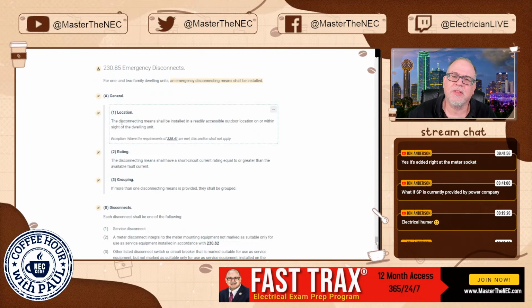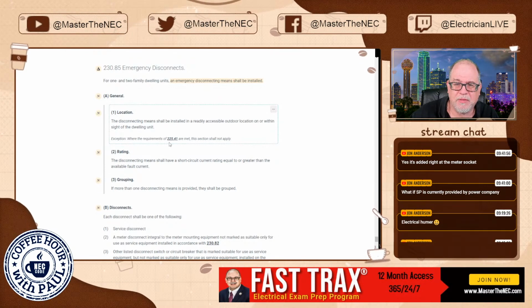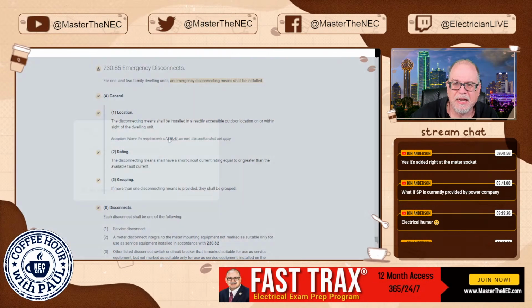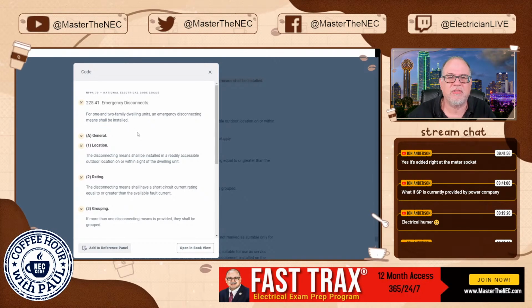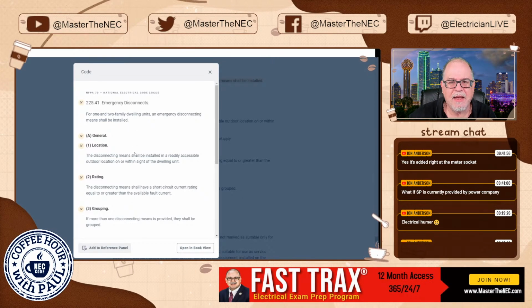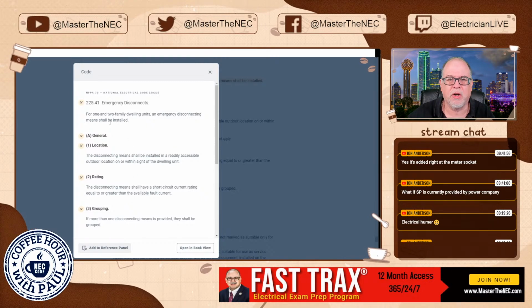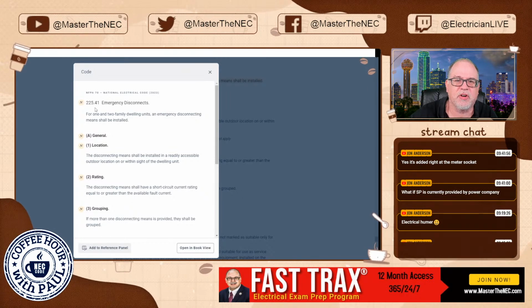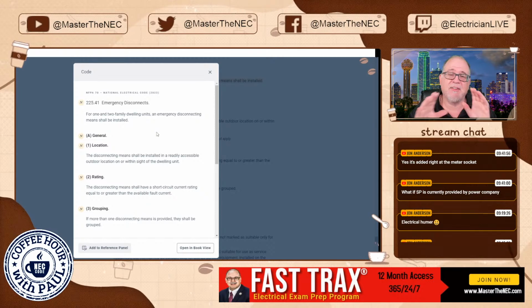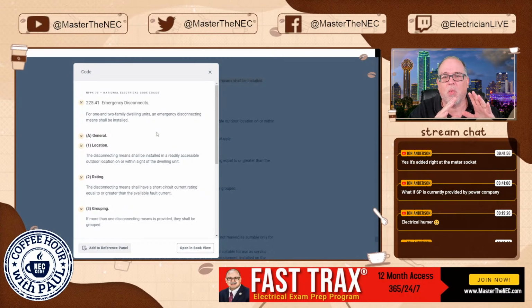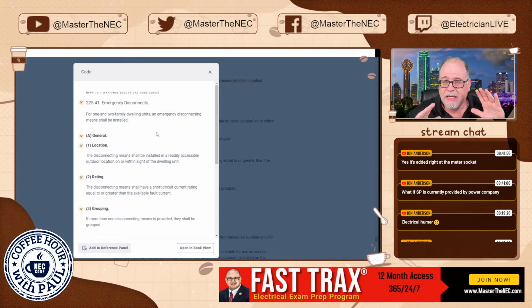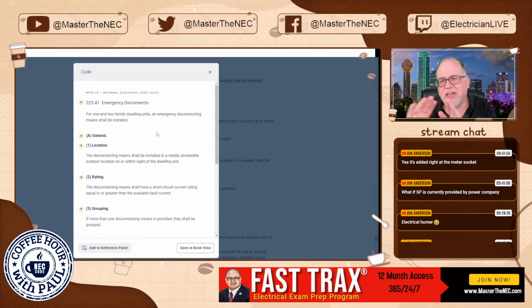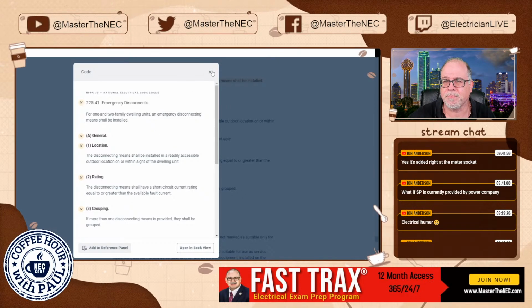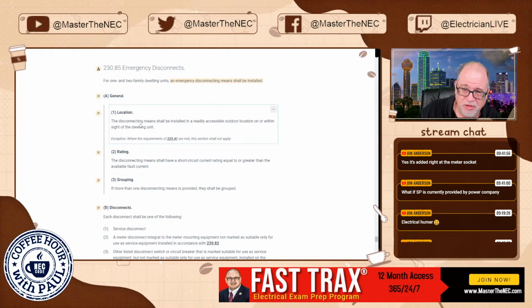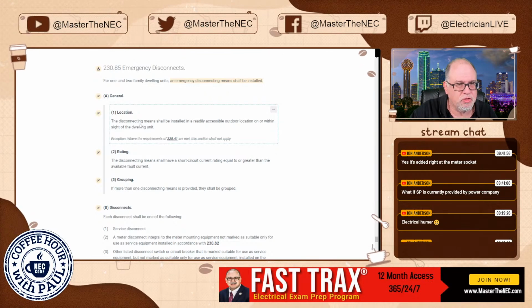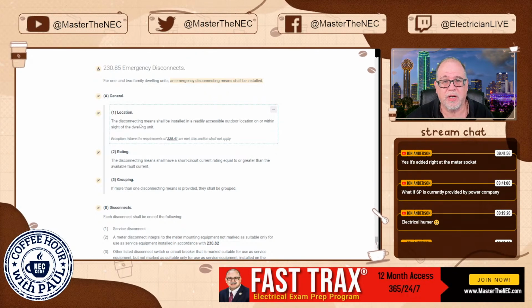Okay. Now, the other thing that it talks about, it says exception to this. It says where the requirements of 225.41 are met, this section shall not apply. And just to remind you what those were, this is the situation where you had what? A feeder type of disconnect, 1 or 2 family units, the emergency disconnect shall be installed. This is under 225. So if you meet that in that installation where, like we said earlier, you have a 1 and 2 family dwelling being fed outside by a feeder, if you've already met that, then you can ignore this because then it's already been met, right? All right, but assuming this is not the case and you're not using 225, then what does that mean? Then you still have to have your emergency disconnect at your 1 and 2 family dwelling.